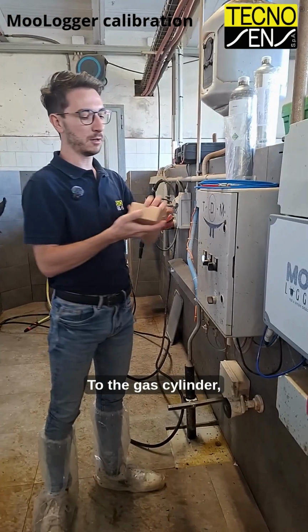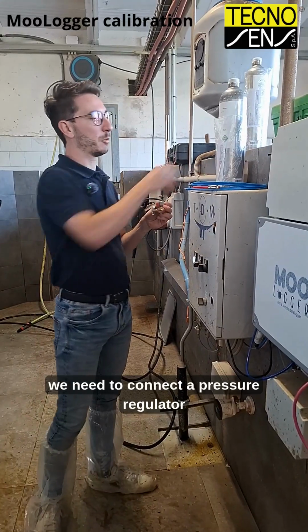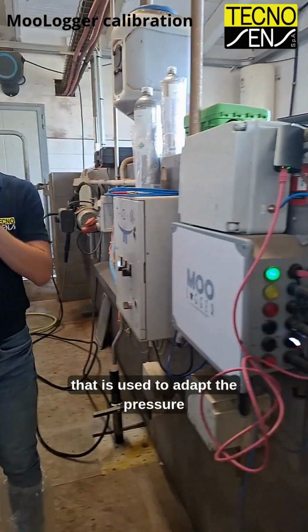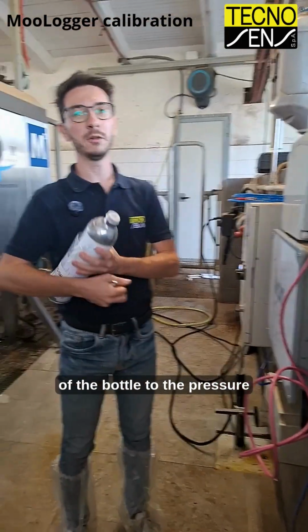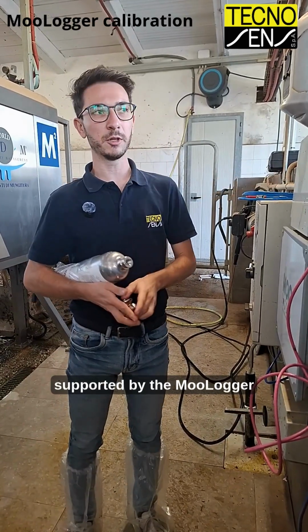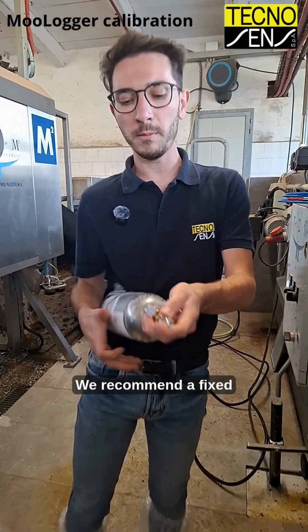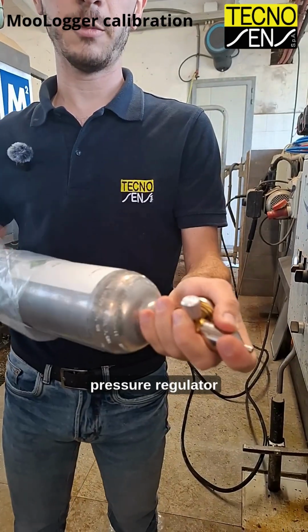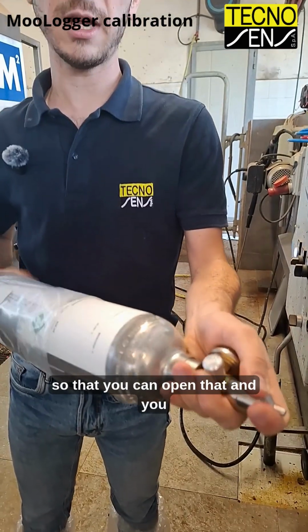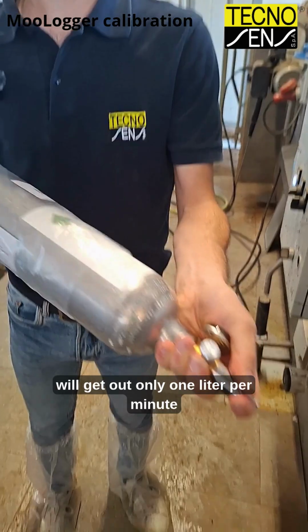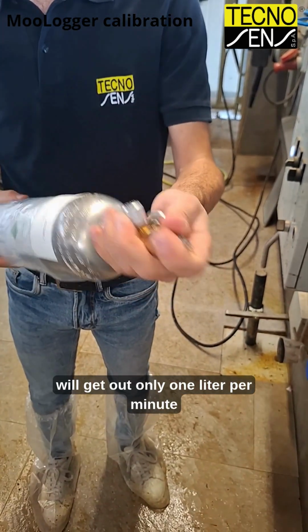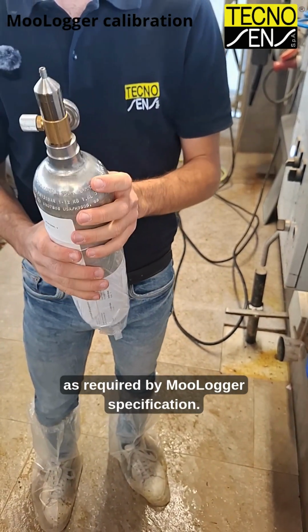To the gas cylinder, we need to connect a pressure regulator that is used to adapt the pressure of the bottle to the pressure supported by the MooLogger. We recommend a fixed pressure regulator so that you can open that and you will get out only 1 liter per minute as required by the MooLogger specification.